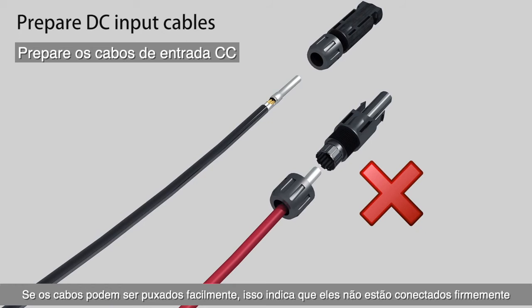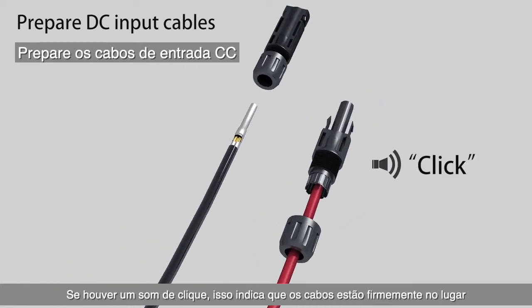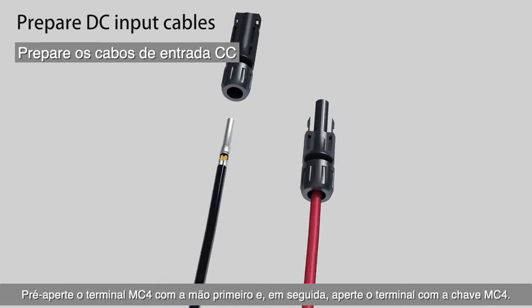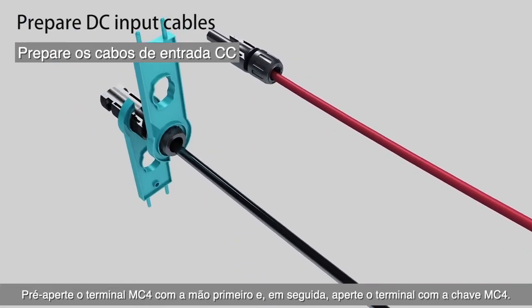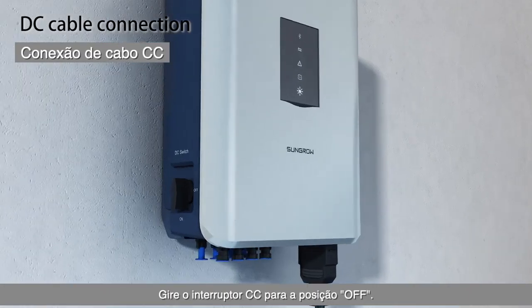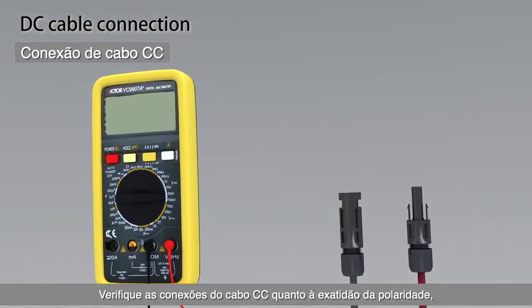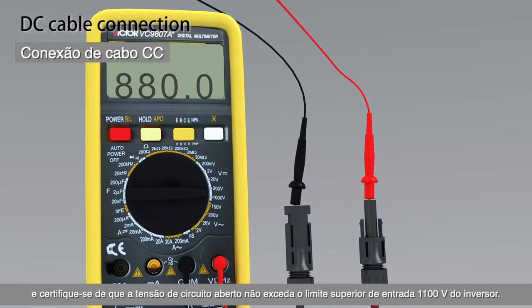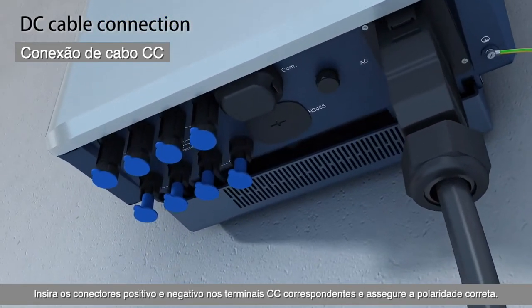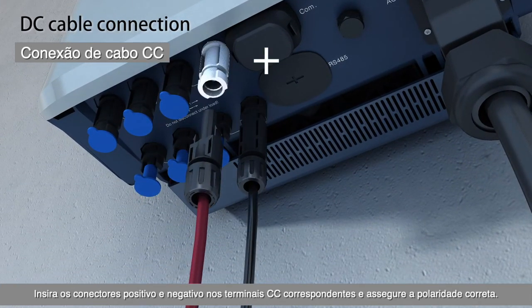If the cables can be pulled out easily, it indicates they are connected infirmly. If there is a click sound, it indicates the cables are firmly in place. Pre-fasten the MC4 terminal by hand first, then fasten the terminal with the MC4 wrench. Rotate the DC switch to the OFF position. Check the DC cable connections for polarity correctness and make sure the open-circuit voltage does not exceed the input upper limit of 1100 V of the inverter. Insert the positive and negative connectors into the corresponding DC terminals and ensure correct polarity.